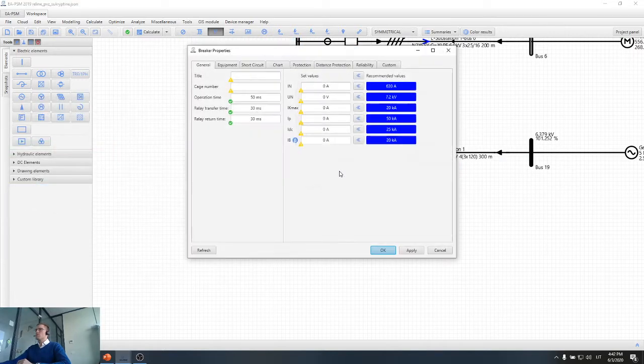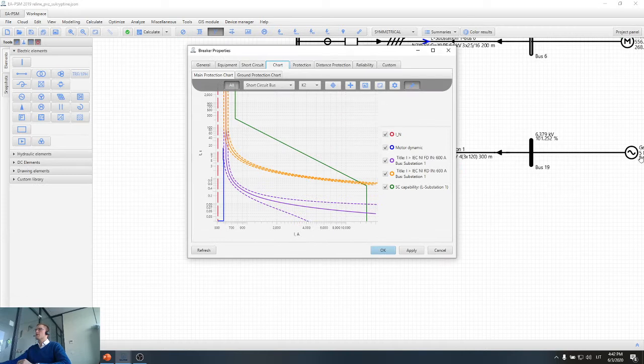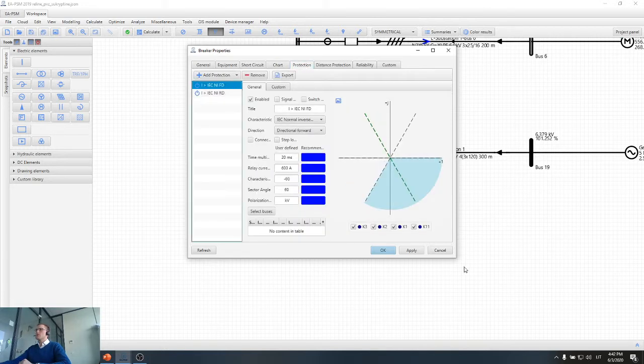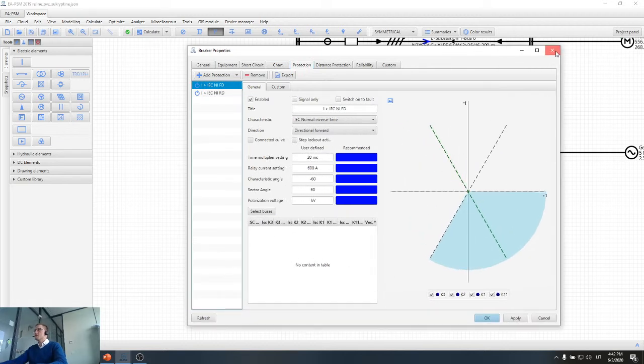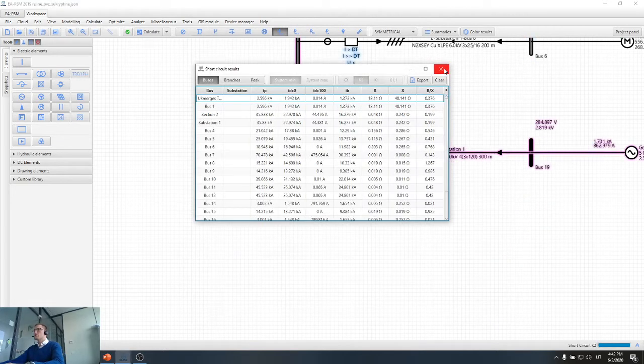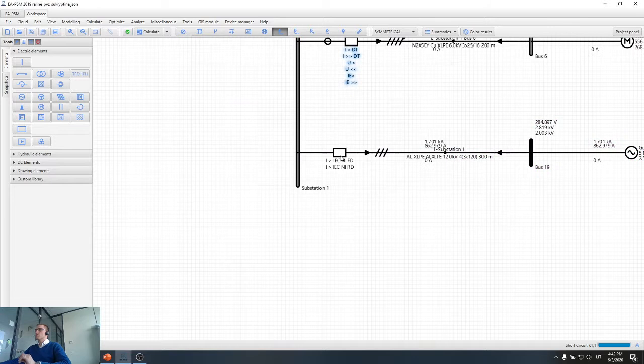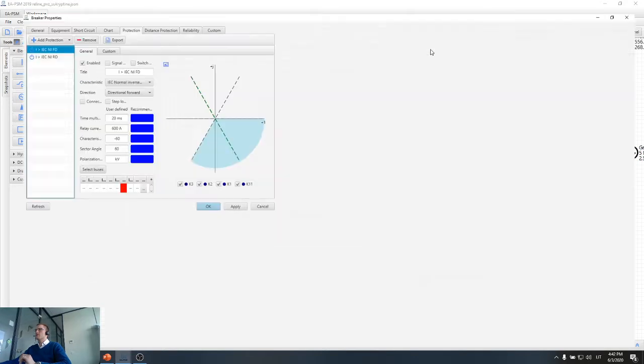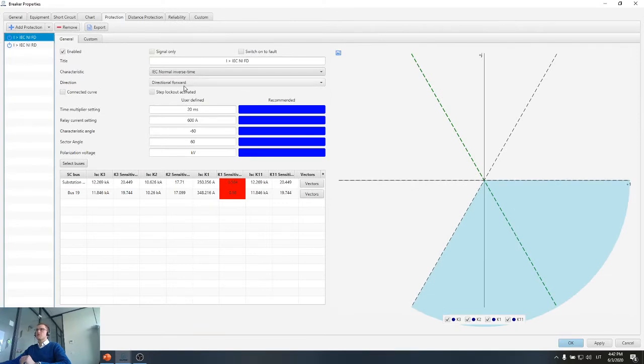So basically, if I open overcurrent protection devices of the generator here, I can see that there are two overcurrent curves provided. And if we go to protection devices settings, before that I will also recalculate short circuits. Basically, I will show quickly about the directional protection devices. So there are two types of directional protection devices, directional forward or reverse. So basically, one is protecting the generator, another is disconnecting the generator from the network in case we have short circuit there.